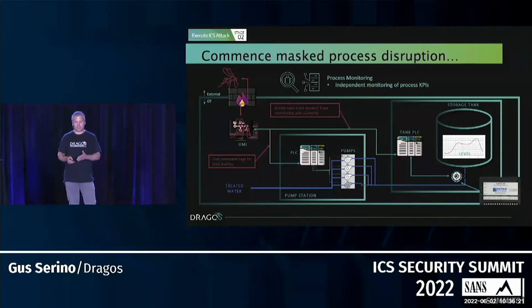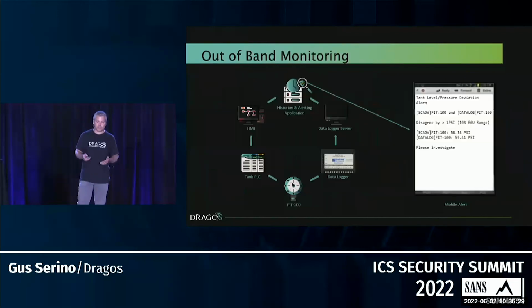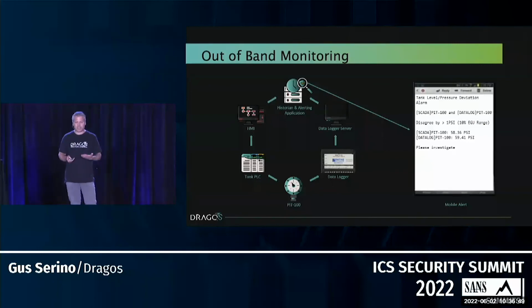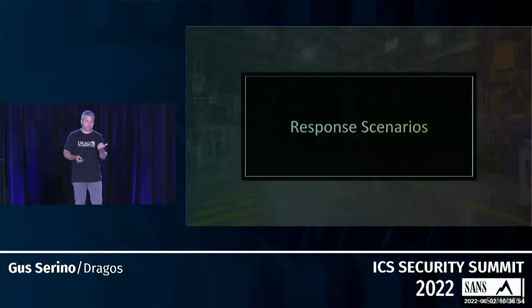So here we have that data logger again, tied to the pressure instrument, sending its own telemetry back to the data logger server. And with the application sitting over the historian that's comparing those two values, it says, hey, I see a discrepancy, and sends an alert by SMS or email to a separate audience, maybe the operators, but also supervisors, engineers, whoever else is going to be looking at this, to say, hey, I think we have an issue, let's go take a look. And that is an important level of situational awareness for those signals that we really care about.